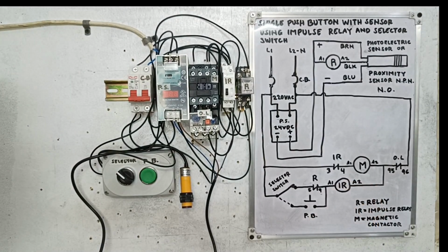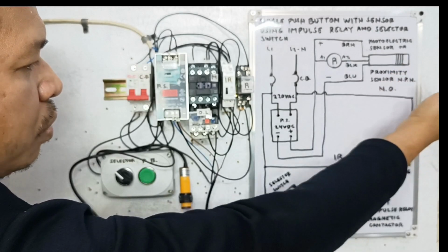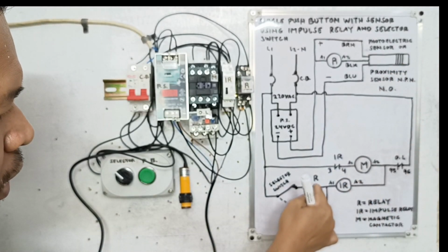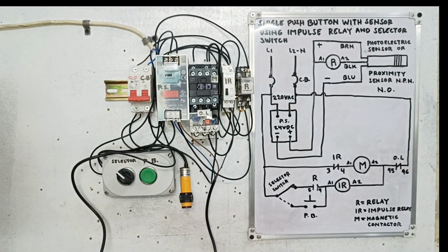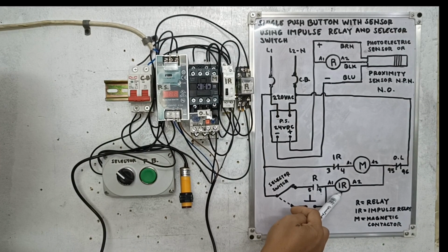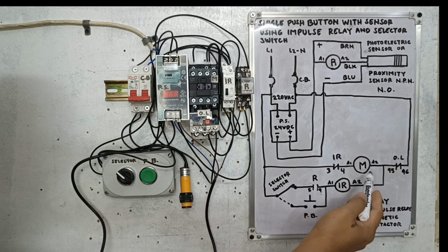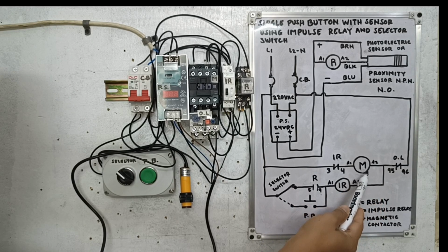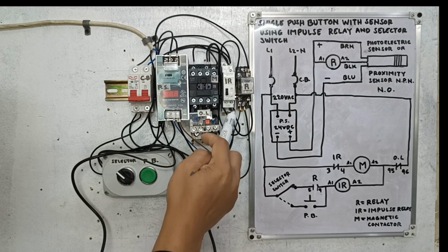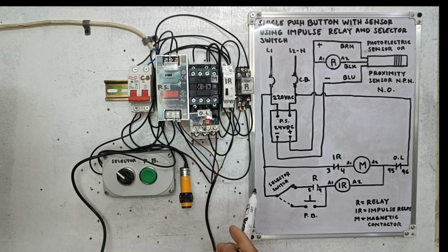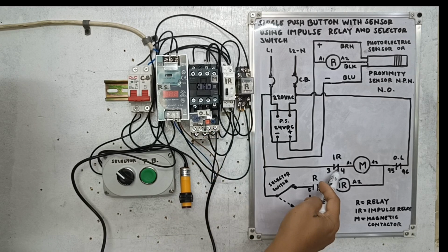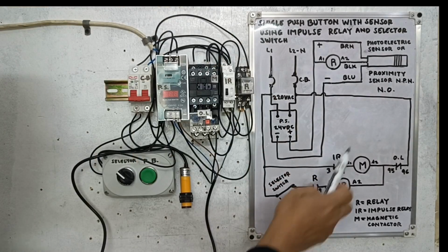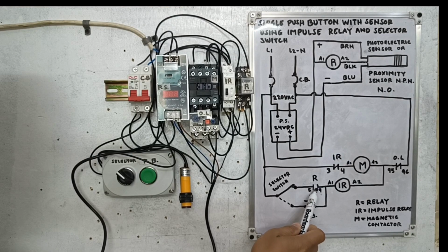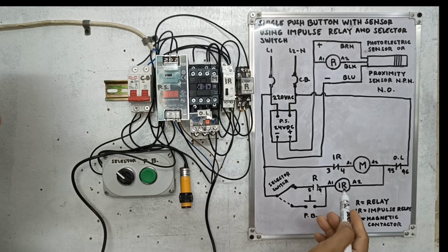It activates also. If the sensor now cannot sense the object, this contact will open. The impulse relay will cut off the power. This one will be off, but the magnetic contactor is still activated because our impulse relay was reset for automatic. If automatic, guys, the contact of this impulse relay will close even though the sensor cannot sense the object and this will open. Now, if the sensor can sense the object again, this one will close again.